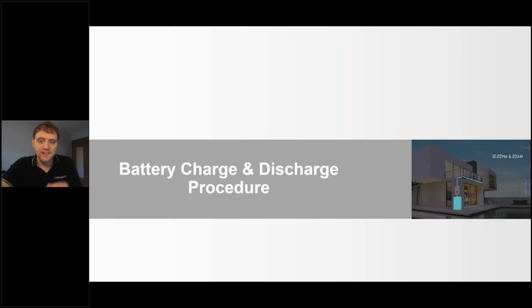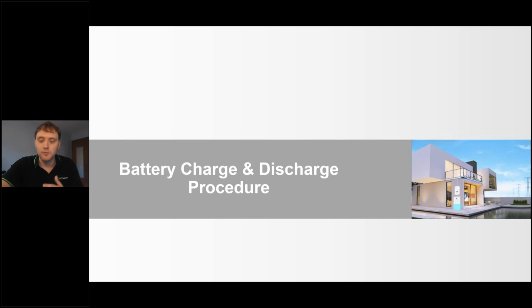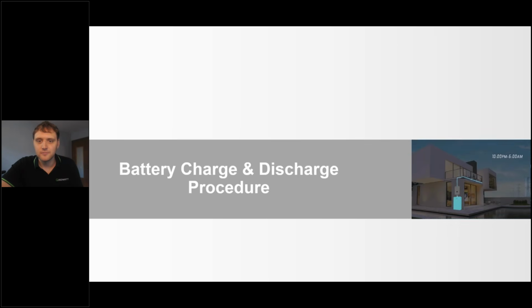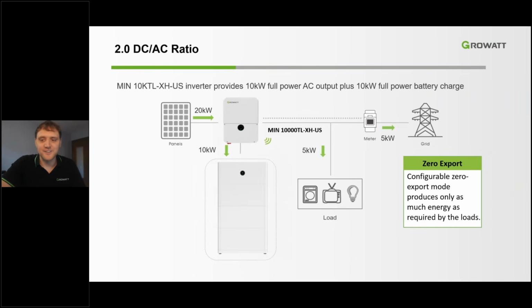So let's put those products together, see exactly how the energy is stored and discharged from the battery. We can take a little bit more of a look at the configurability of these systems. As we discussed earlier, the MIN has a 200% DC to AC ratio. A 10 kilowatt inverter can accept a 20 kilowatt array to maximize the usage of space on the roof. While PV production is at 20 kilowatt, the 10 kilowatt inverter is able to output its full power to the load center of the home and charge the battery with an additional 10 kilowatts of power. This is exceptional, absolutely, as your customer can charge the battery, be self-consuming, and sell energy to the grid all at the same time. We will talk more about the backup functions of this product very soon, but the grid is not totally necessary for the operation of these functions.